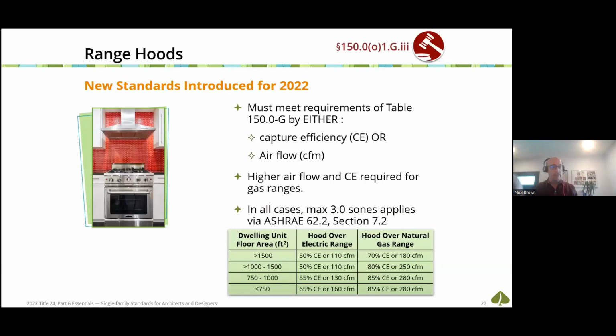And here's a slide from one of my Energy Code ACE classes on spot source mechanical ventilation, specifically kitchen range hoods. This is a mandatory requirement new for 2022. And you'll see that it sets higher minimum airflow than in past code cycles. Used to be 100 CFM met the standard. Now it's up to 280 CFM. And this table below, you'll see, asks for higher airflow over natural gas ranges than electric ranges, in recognition of the fact that gas ranges produce additional pollutants relative to electric ones.